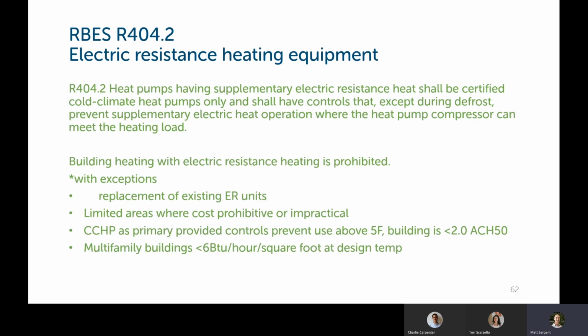Cold climate heat pump primary provided, controls prevent use above 5 degrees. So if we have a building that's less than 2.0 ACH 50 and we have a cold climate heat pump as the primary heating source, we need to install controls that will prevent the use of the electric backup heat above 5 degrees Fahrenheit outdoor air temperature. And multifamily buildings less than 6 BTUs per hour per square foot at design temp. I think Charlie pointed that out earlier. There's an exception for the electric resistance prohibition for those units as well.